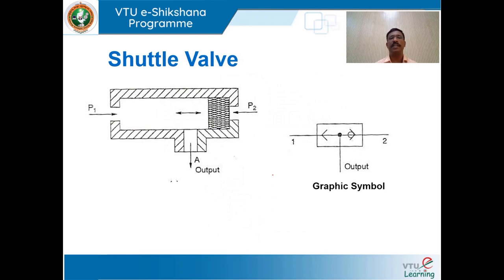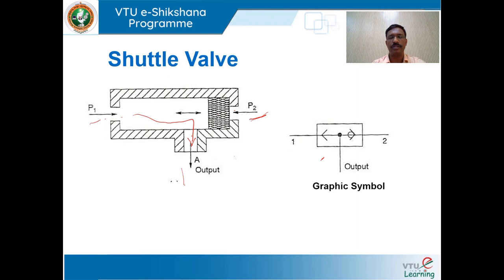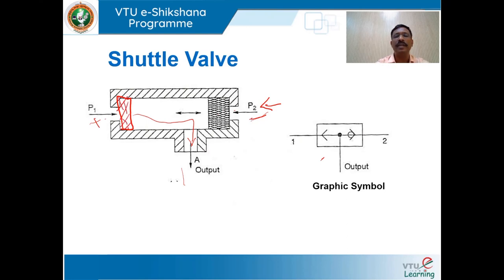We shall discuss a special type of directional control valve — the shuttle valve. It has a primary port P1, secondary port P2, and an output port. A ball toggles between P1 and P2. When signal is present at P1 and no signal at P2, P1 connects with A and the system is pressurized. When there is no signal at P1 and signal at P2, the ball toggles and blocks the P1 opening — P2 connects with A.